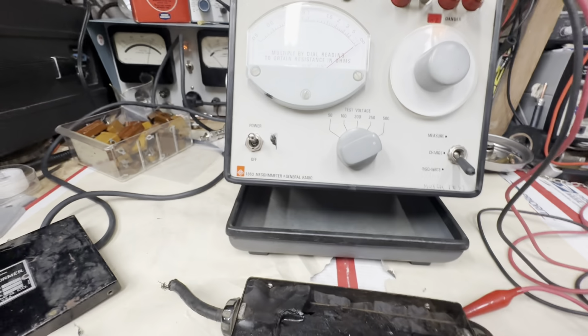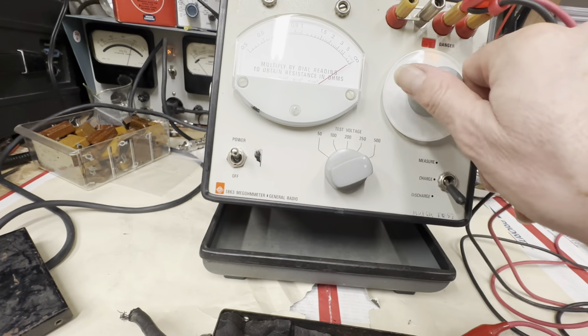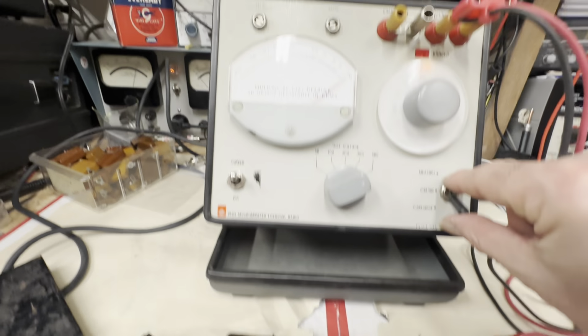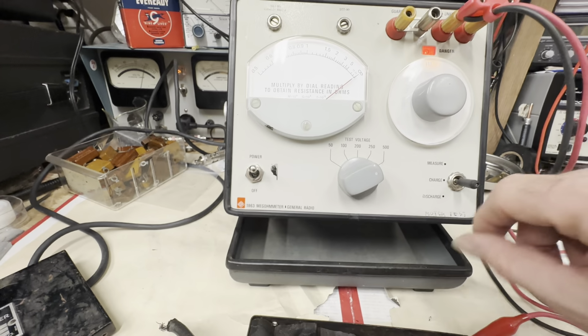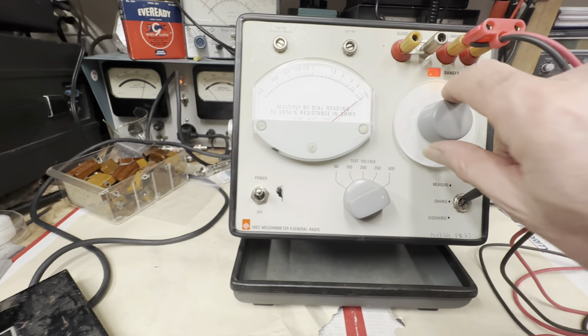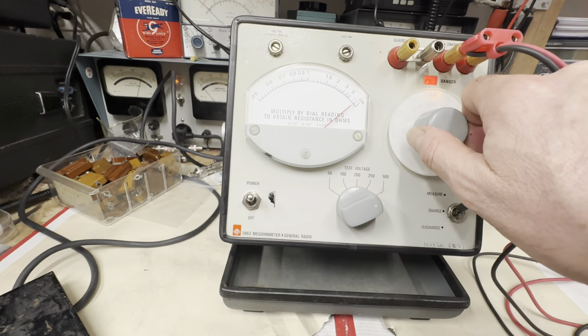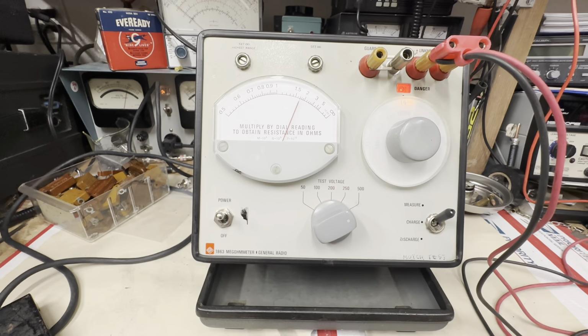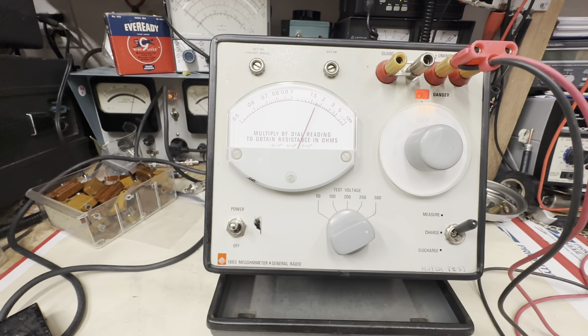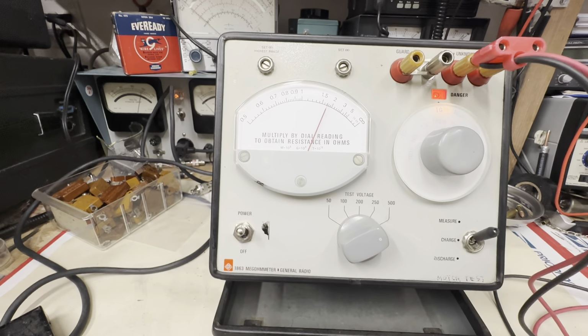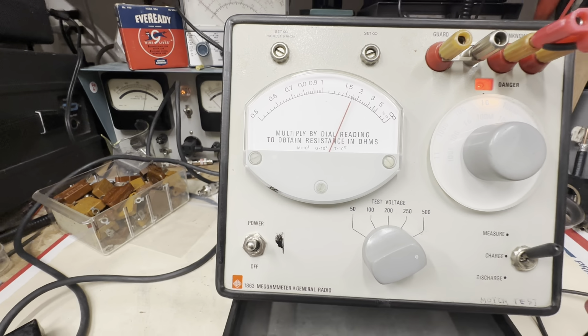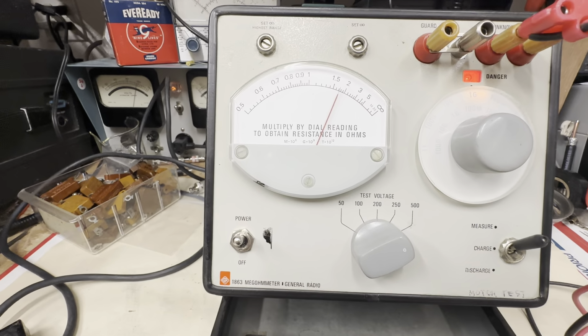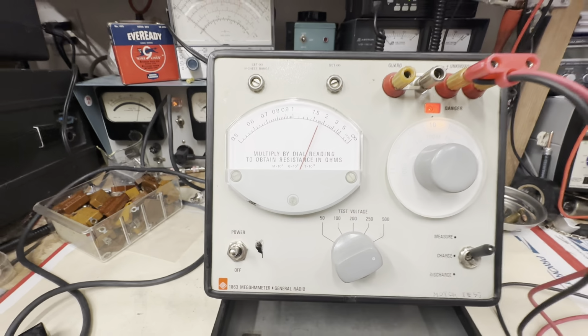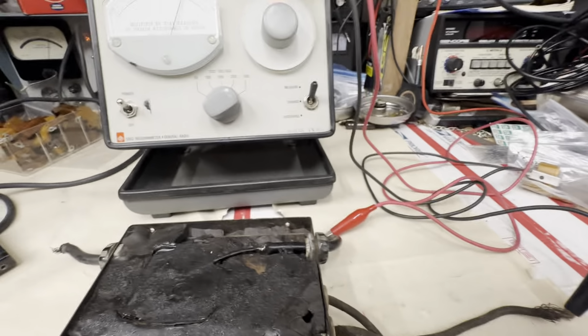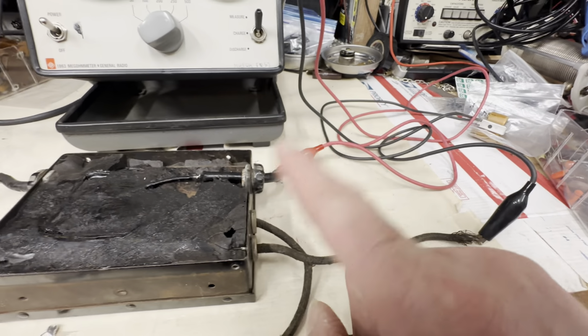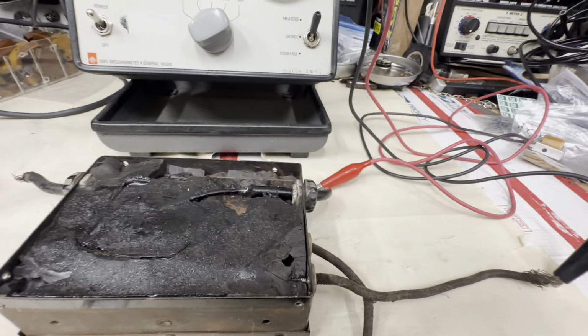And we definitely want to check this thing at the highest possible voltage that we can. So we're going to be at 500 volts, charge it up, boom. It took a little spike there as it charged. And there we go. Let's go up here. Oh, look at that. Right there, we're at about 1.7 gigs. And you can see it's very, very slowly climbing up due to dielectric absorption there. Okay, so we see right now that essentially there's no path between the secondary and the primary, so that's good.